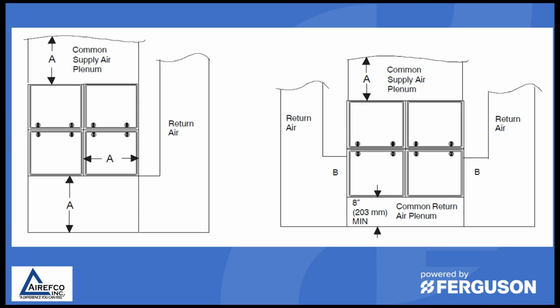Airflow is extremely important in any installation with a gas furnace or fan coil. Especially when twinning gas furnaces, airflow becomes a very important factor. In the diagram on the left, you have a return air on one side of the furnace, as long as you have the distance for the can the furnaces are going to sit on. If you don't have the distance, then on the right-hand side, it's shown with two returns on both sides with a small 8-inch can on the bottom.